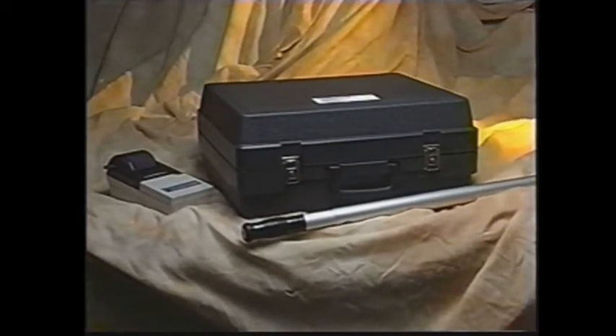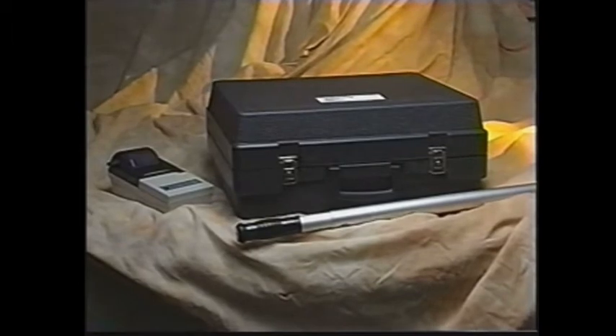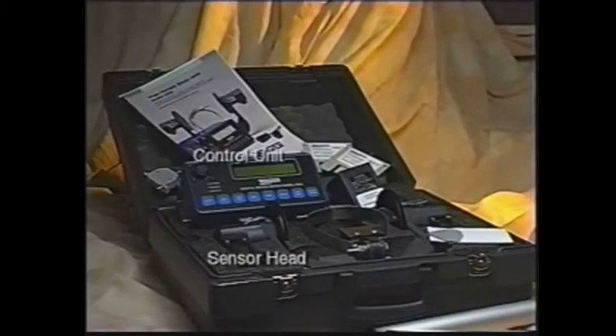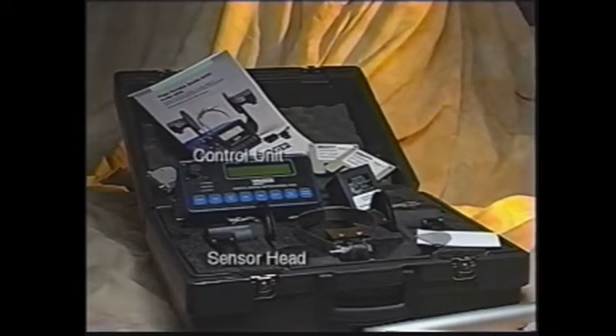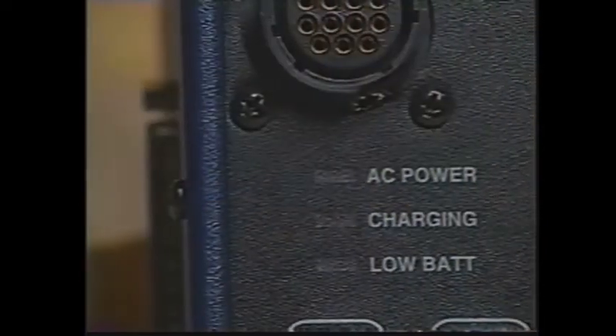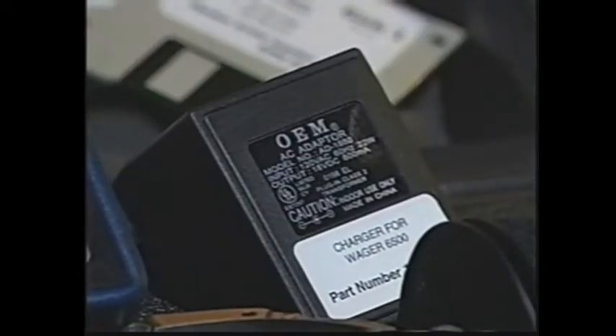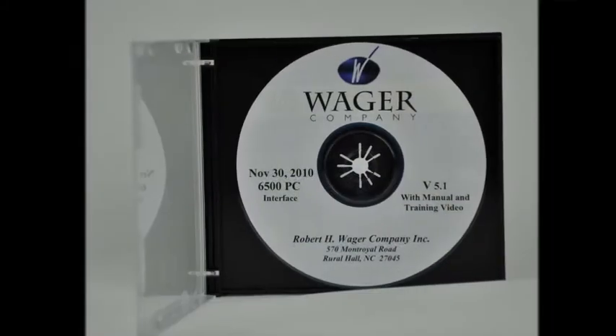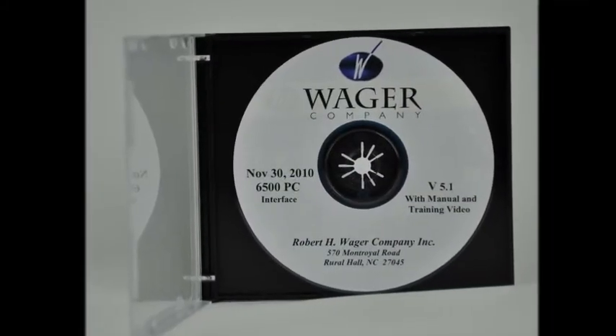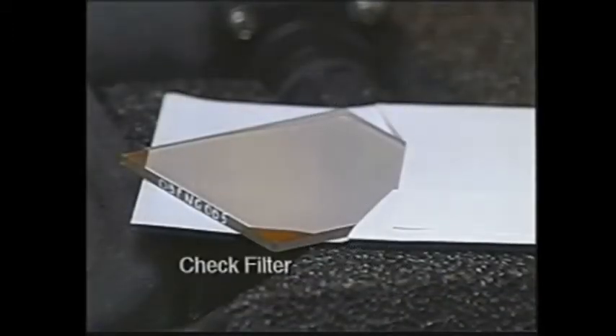We also include an impact printer and an extension pole. The control unit connects to the sensor head assembly. You can operate the unit on direct current or about 40 hours on a full battery charge. The system also accepts an interface to your computer. We supply you with a check filter to verify the accuracy of calibration.